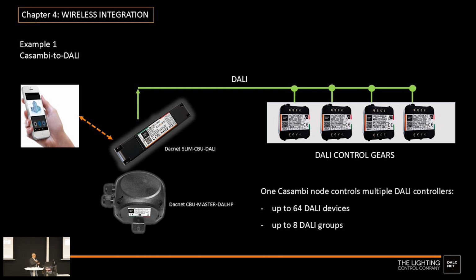So this kind of device is very interesting, especially if you're dealing with Casambi. Another reason for combining DALI and wireless is that in a wireless project, sometimes you have areas you cannot cover with a Bluetooth signal because there are walls, metal parts, or building barriers. So it's useful to have the Bluetooth device in a reachable area, and then use the wire to reach places not covered by the wireless signal.